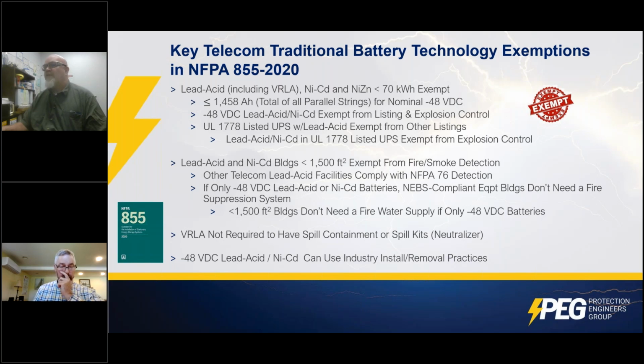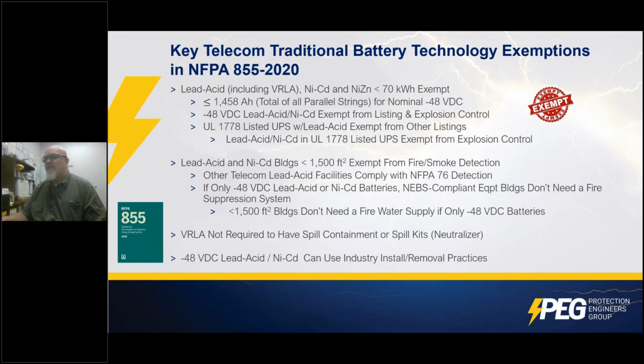If you have a UPS and you're a telecom company, because telecom companies have UPSs too, if they used lead acid or NiCad in a UL 1778 listed cabinet, those are exempt from the explosion control and other listings as well. In very small buildings, the lead acid and NiCad were exempt from fire and smoke detection. And as long as the lead acid facilities complied with NFPA 76 detection requirements, which are fairly stringent, then lead acid was exempt from most of the fire and smoke detection. NEBS compliant equipment buildings, in other words, if all the equipment's NEBS compliant, it's flame retardant, and so they don't need a fire suppression system. They have to have fire and smoke detection, but they don't need a fire suppression system.